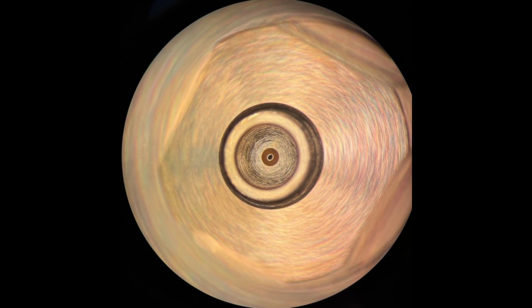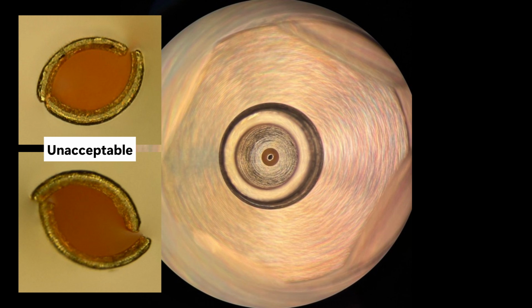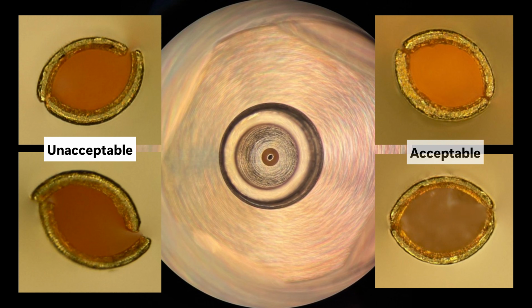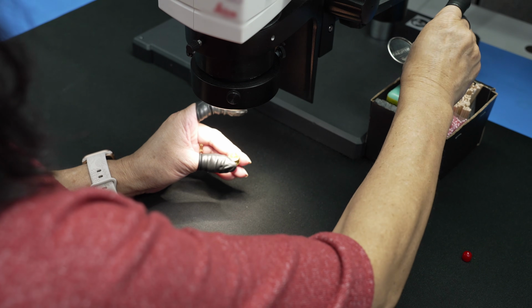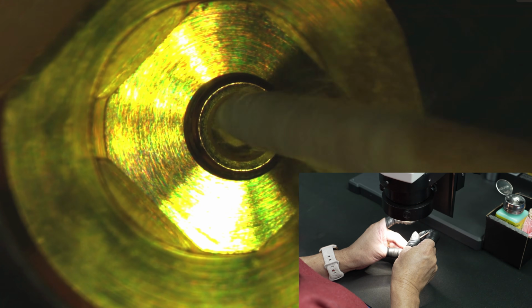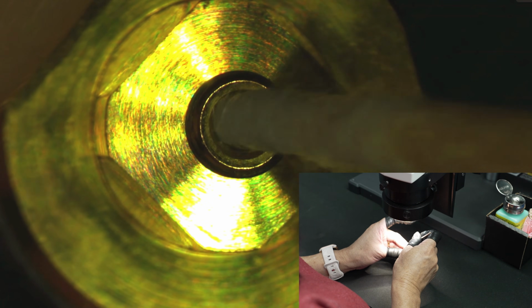The female contacts should be symmetric. Here's an example of asymmetric and unacceptable contacts, and an example of symmetric acceptable contacts. To clean the device, use a clean cotton swab dipped in isopropyl alcohol and gently clean the mating surfaces. Take care to avoid the center conductor.